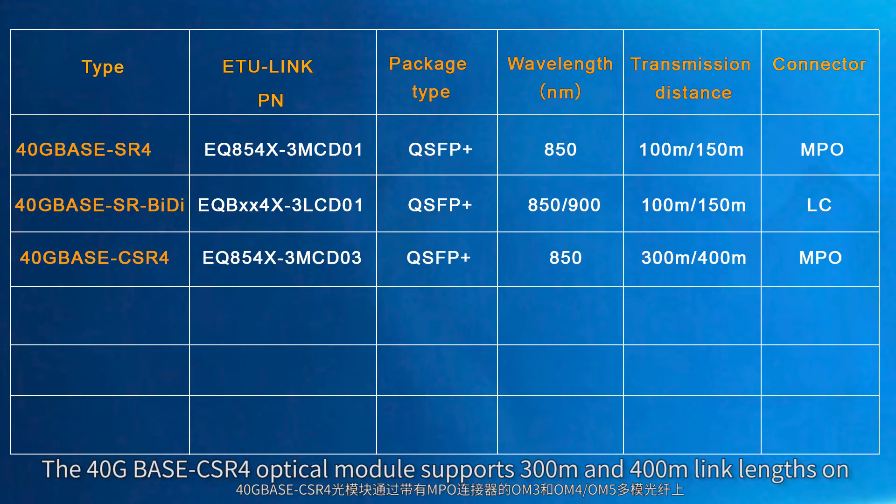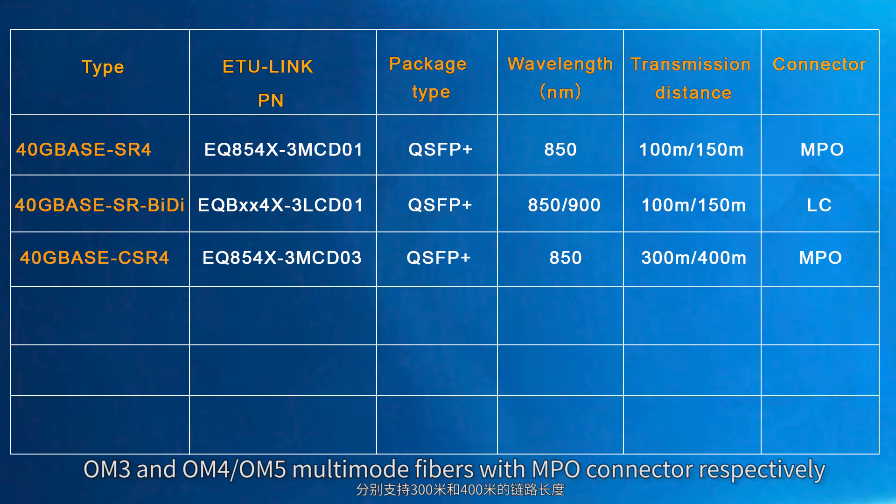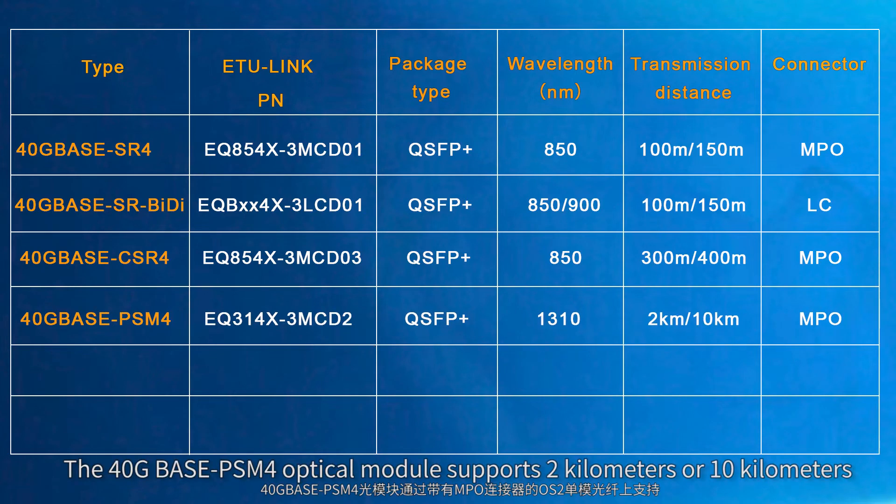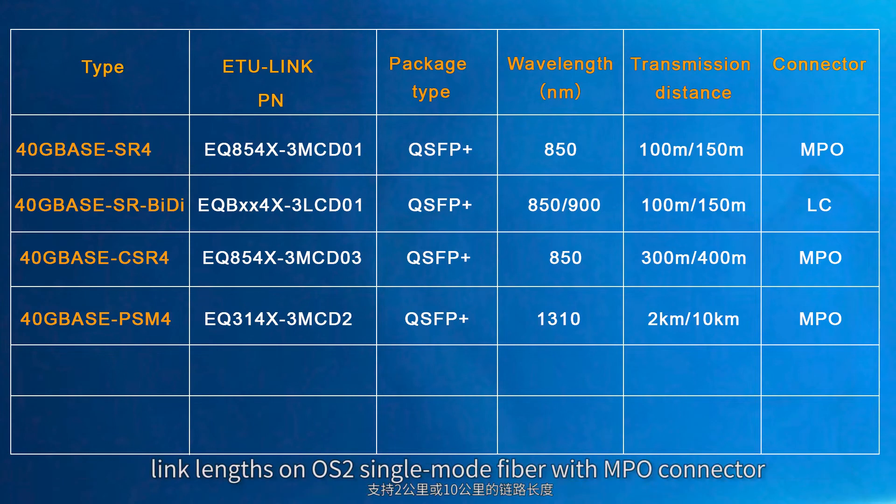The 40 gigabit base CSR4 optical module supports 300 meters and 400 meters link length on OM3 and OM4 or OM5 multimode fibers with MPO connector respectively. The 40 gigabit base PSM4 optical module supports 2 km or 10 km link length on OS2 single-mode fiber with MPO connector.